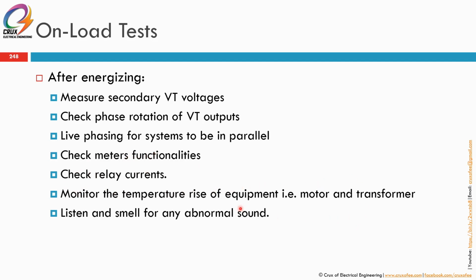This is for motor and transformer lah. Once you loaded them up, you will monitor the motor and transformer temperature rise to see that they will rise and stabilize within a stable operating temperature. And for the next 24 hours to 72 hours, normally you will place someone to oversee the progress of the on-load test, and also listen and smell for any abnormal sound, because sometimes the fault may happen immediately right after you energize, but sometimes the fault may happen a few days later or months later.